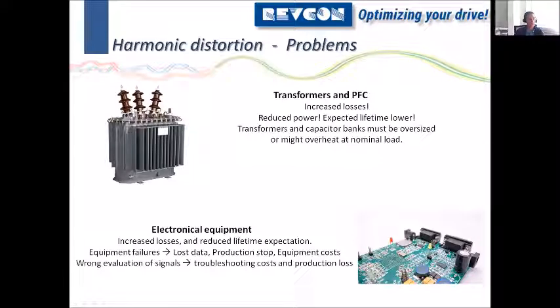It's basically the same for power factor correction. A capacitor direct online would always take the current that is the shape of the voltage. So if you have this shape on the voltage, then the capacitor will just pull the same current. And you will see a ripple on your power factor correction, on your capacitor, and that will reduce the lifetime of the capacitor quite significantly. So as a result, you have to oversize this kind of equipment, or, looking at the PFC, you would have to replace it earlier than you should need to.